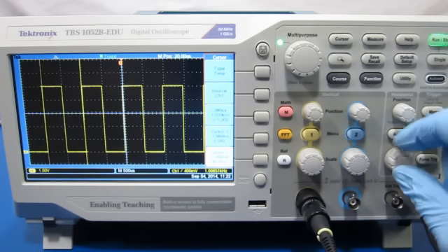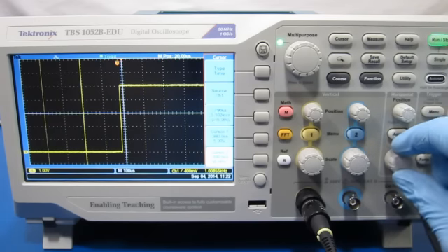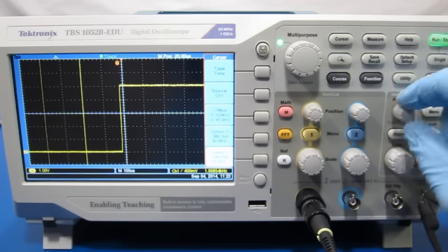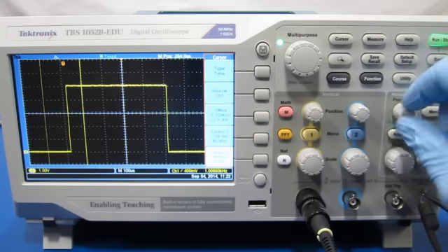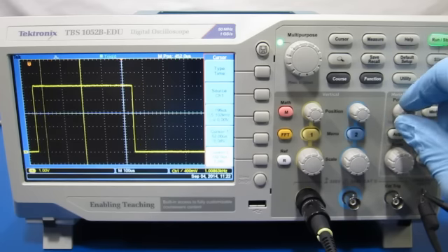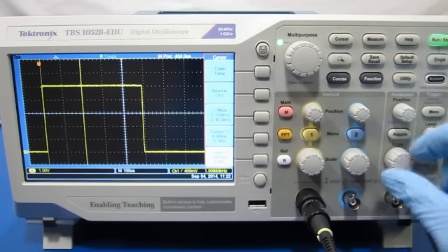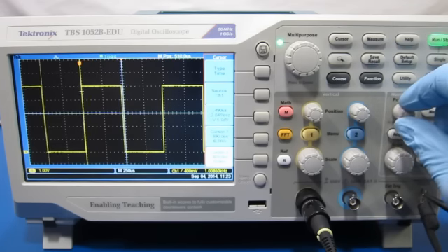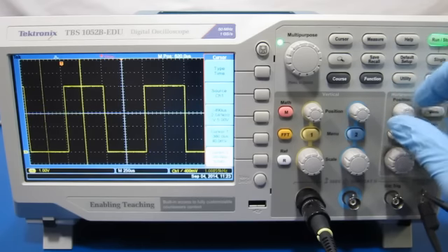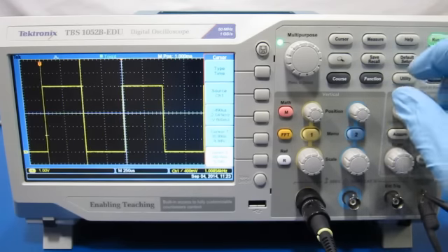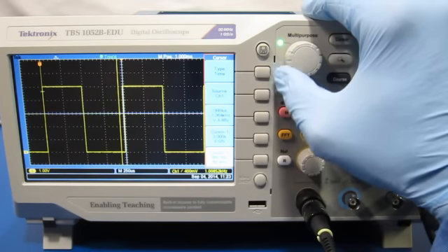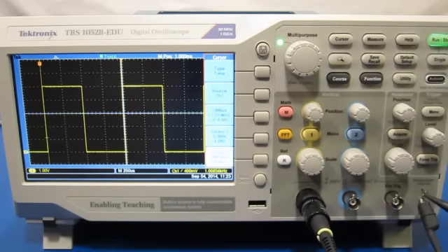That seems a little off to me, so we're going to expand it out and get a little bit better. See if we can adjust our display here to get a full trace. Doesn't look like we're going to make it, so we'll do one less here. Okay, and then cursor number 2. And then that says we're 1.01 kilohertz or 990 microseconds. So that's what the cursor tells us.